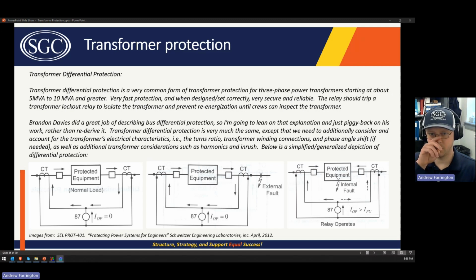especially if it's a power transformer, not like a generator. Generators may have transformer differential protection even below 5 MVA, but for distribution and power transformers, you're usually looking at around 10 MVA and greater. You start to protect the transformer with breakers and differential protection and overcurrent protection rather than fuses.